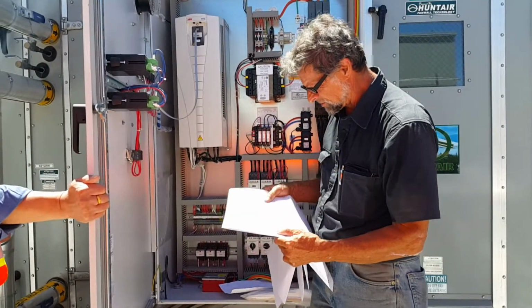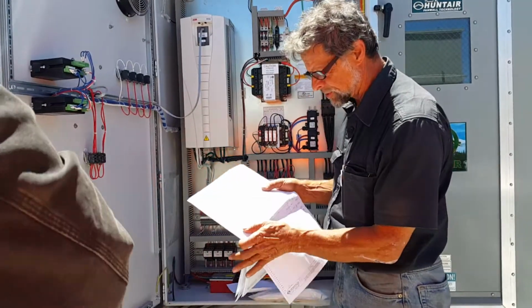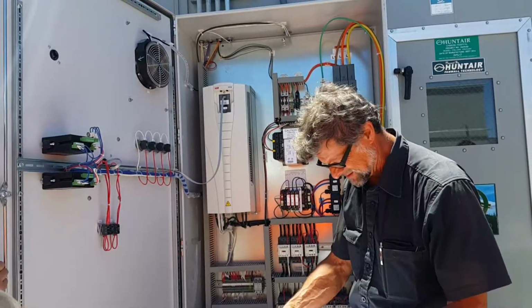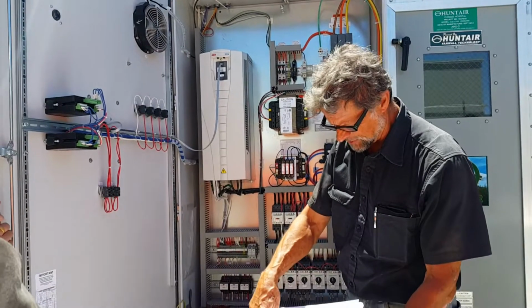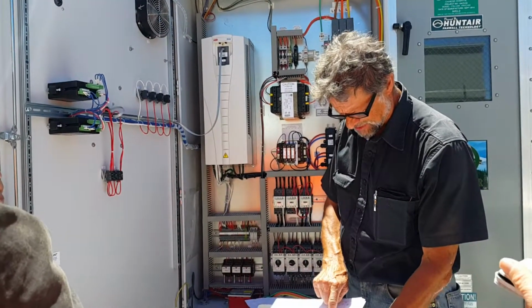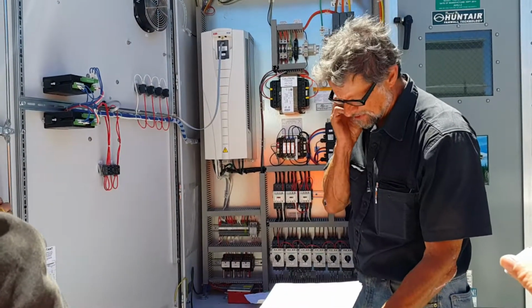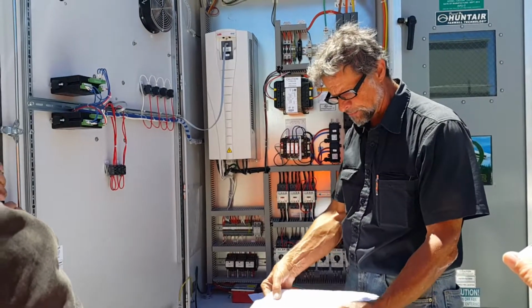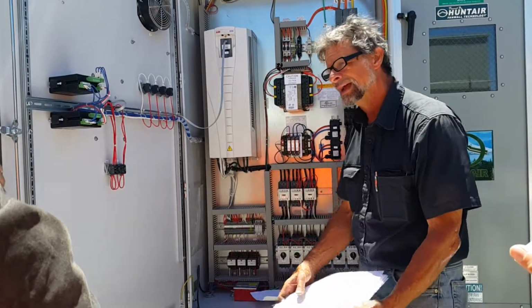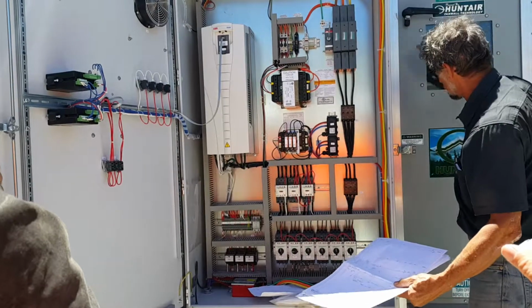The external fault indicator is only on CR3, the same relay we talked about earlier. Again, if that safety line is open in any way, that light comes on. So that's going to include whatever safeties have been field installed and this door switch. I don't know if it's on this door.